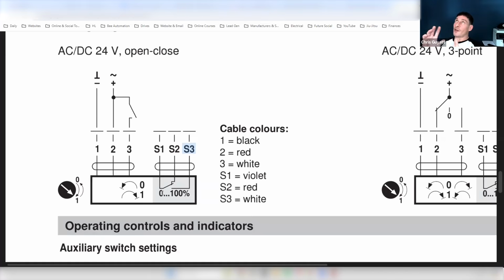Yeah. So just change your wording slightly, mate, just to clarify for people. It's not necessarily demand, because the demand comes from elsewhere. But you're right in what you say. This S3, if we connect a cable into S3, when this actuator is fully open, 100%, that switch will switch, and then we can send a signal out on S3, and we can do whatever we need to do in the rest of the system to tell us that the vent we're looking at in this situation is fully open. And we can also do exactly the same thing. We can send a signal out on S1 when that vent is fully closed.